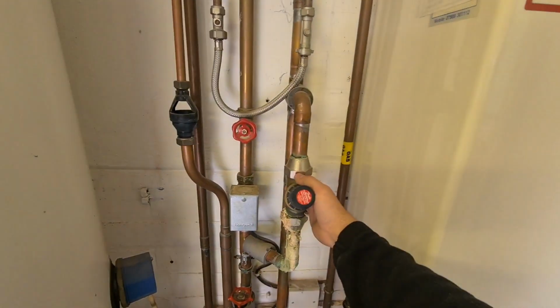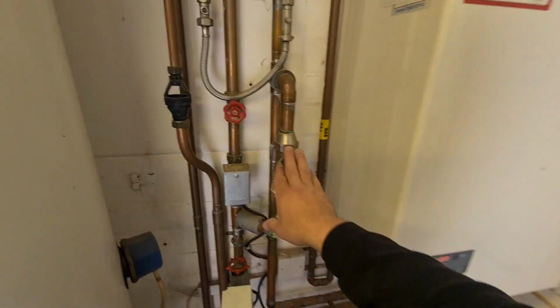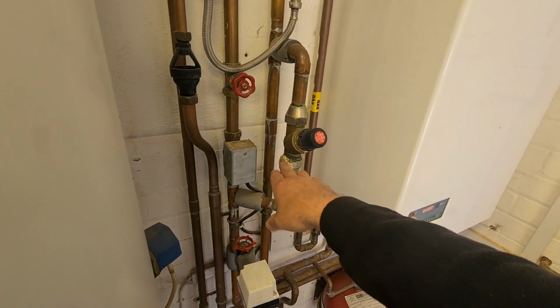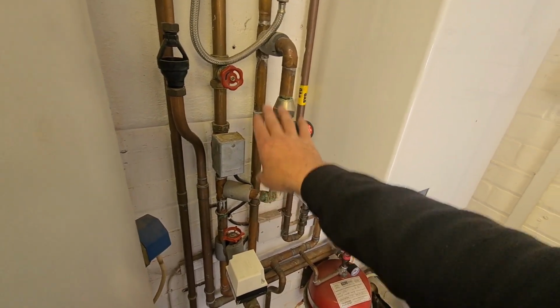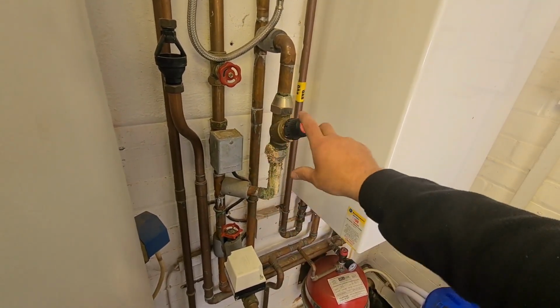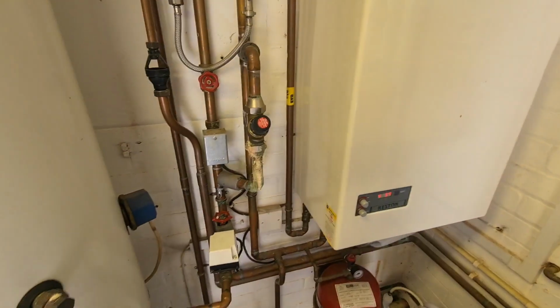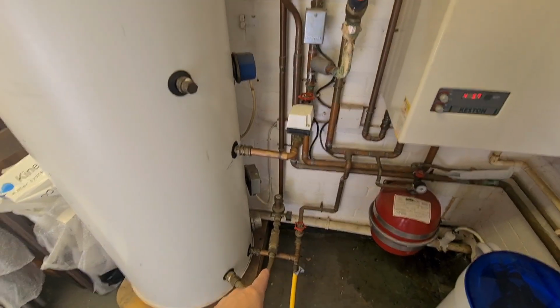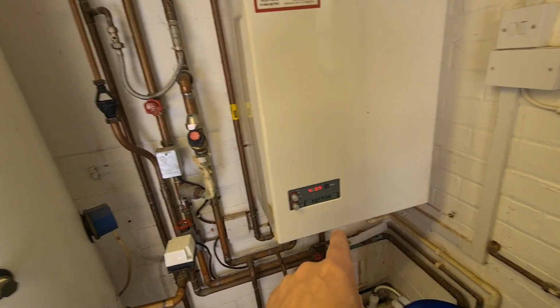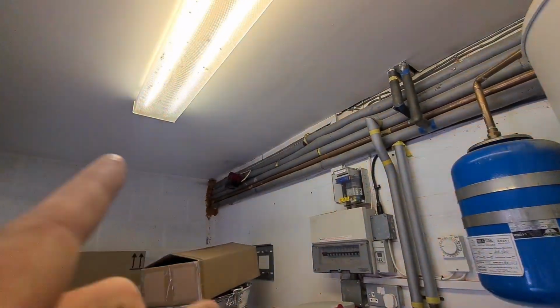So my job today, my bypass is going. I'm going to get this cut out, put a gate valve there. A gate valve, again, I don't really rate bypass valves, I'll be honest, because once these go they can create issues. I can balance the system out correctly today, shutting the bypass down there, the gate valve should I say. I'll be able to create a continuous flow around the cylinder now, and I'm certain that I'll get rid of the pump up there, and the pump in the boiler can make this full system work.